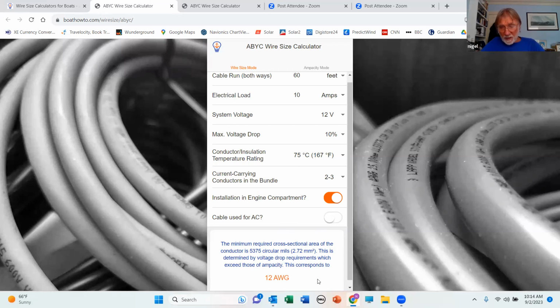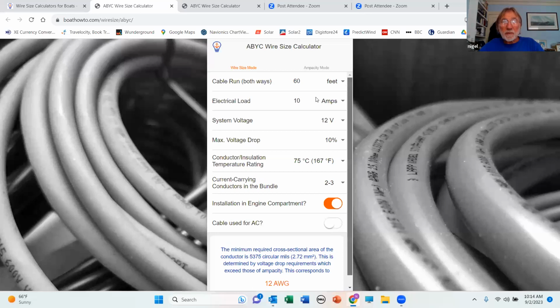So what does that mean? When we do this analysis, we look at the conductor sizing from a voltage drop perspective, and then we look at the conductor sizing from an ampacity perspective. If we go ahead and put those 10 amps through this conductor, are we going to melt down the insulation? Whichever one of those requires us to put in the larger conductor drives the sizing process. And in this case, the table here is telling us that the voltage drop requirement is driving the process. Let's say I shorten that conductor run. I'm going to put it down, just for argument's sake, to 10 feet and see what happens. And then I go back down here. And now, look what's happened.